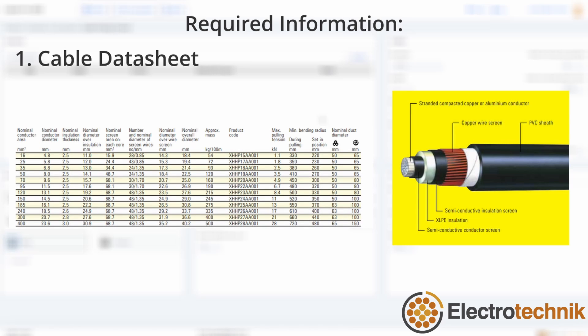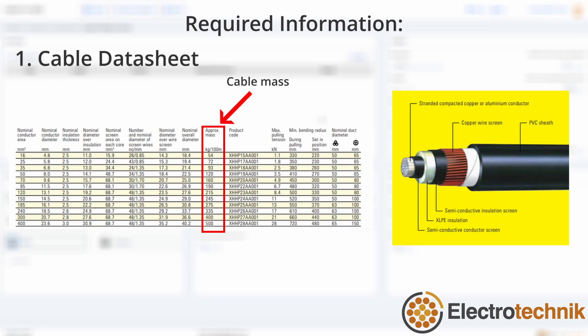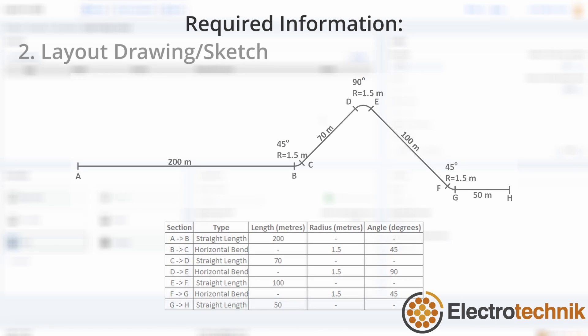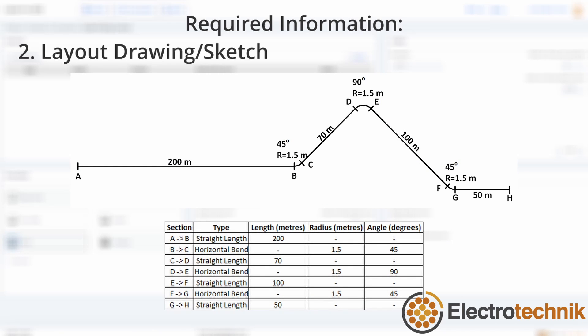To perform a cable pulling calculation, you will need a manufacturer datasheet for the cable, which includes the overall diameter of the cable, weight of the cable, and maximum allowable pulling tension. You also need a layout drawing or sketch of the pull, which is ideally broken down into sections such as straight lengths, bends, rises, and falls. The sections of the diagram on screen are displayed in the table below.